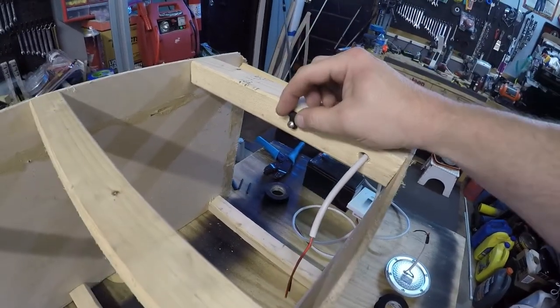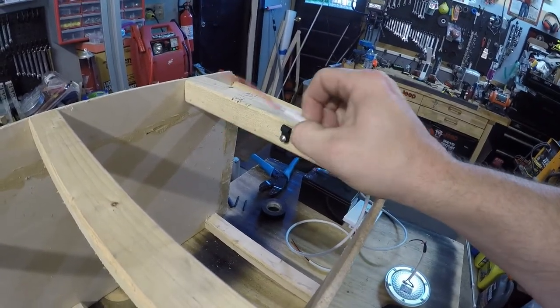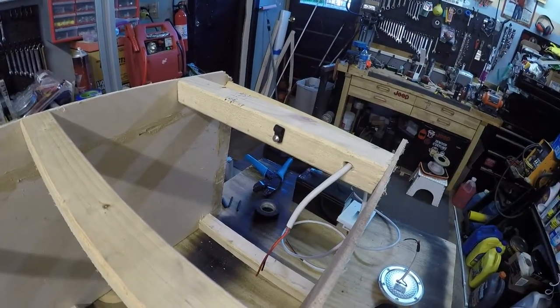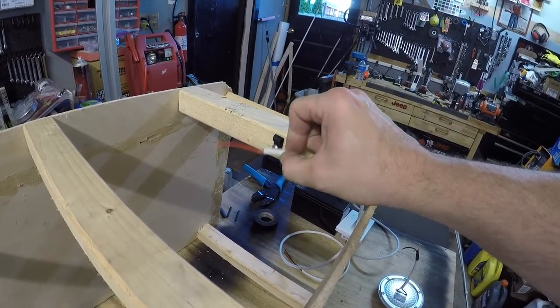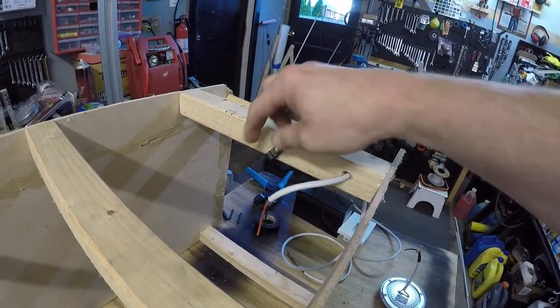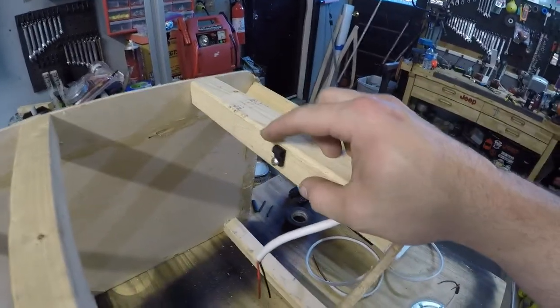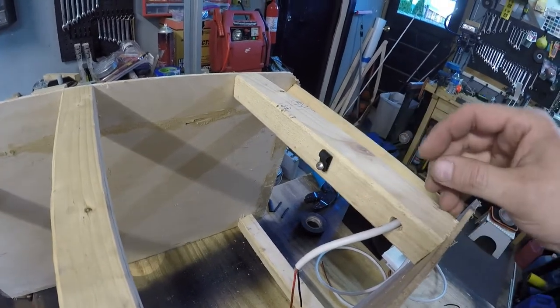I use these little clips to hold the wire — I don't use staples because if you nick the wire you can create a short, and you don't want that inside your roofing material. You want to keep everything nice and tidy. Don't use staples or other sketchy items. You'd run it through there, and once it's where you want it you just screw it in and it tightens right up. They make different brands — you can get them on Amazon or eBay, really cheap, like a hundred for three or four bucks.